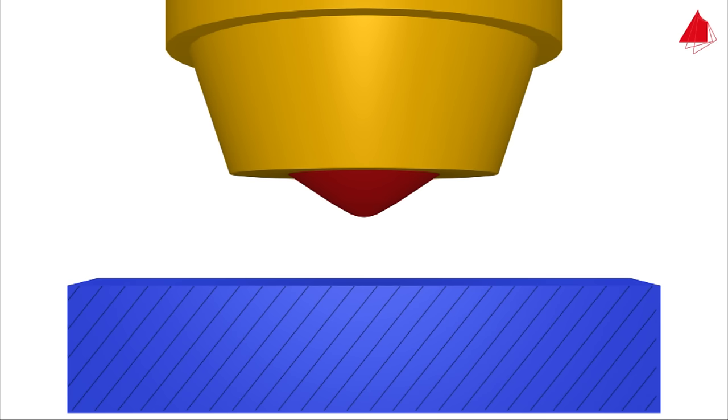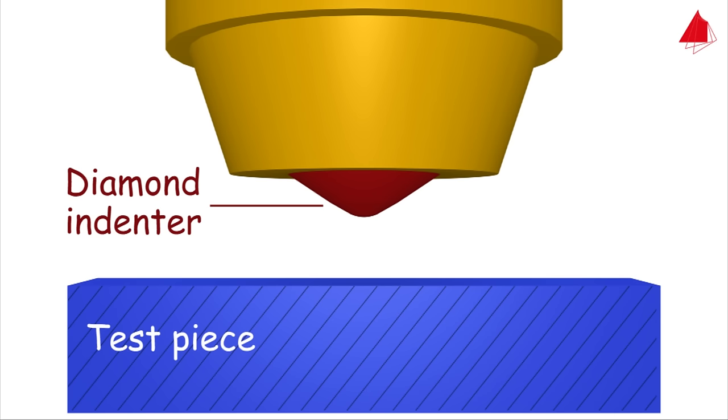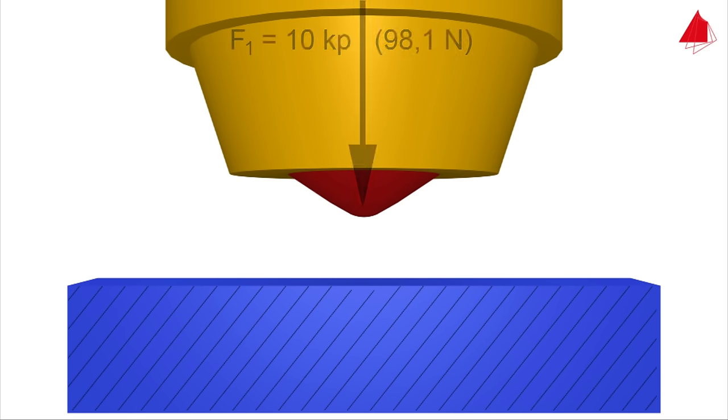In the process variant scale C, a rounded cone made of diamond is used as an indenter. In step 1, the diamond cone is pressed onto the test piece surface with a minor force of 10 kiloponds. The depth of indentation under this preliminary load is the reference point.